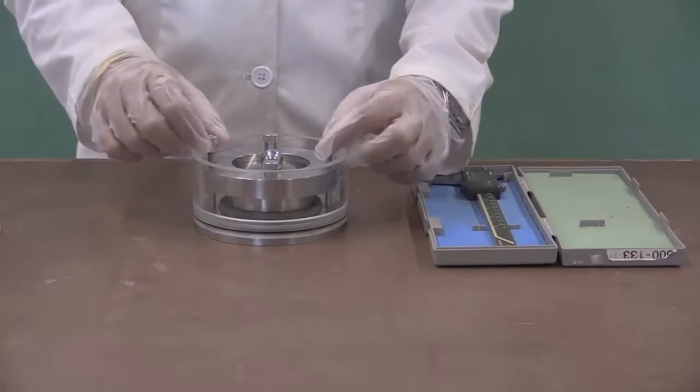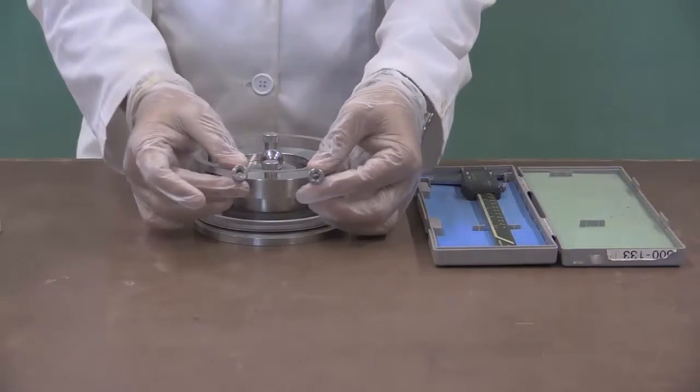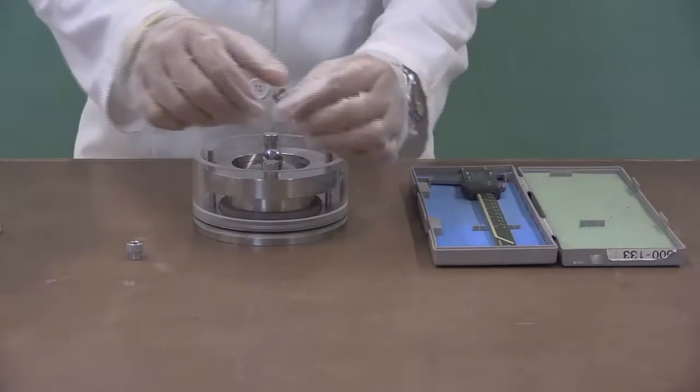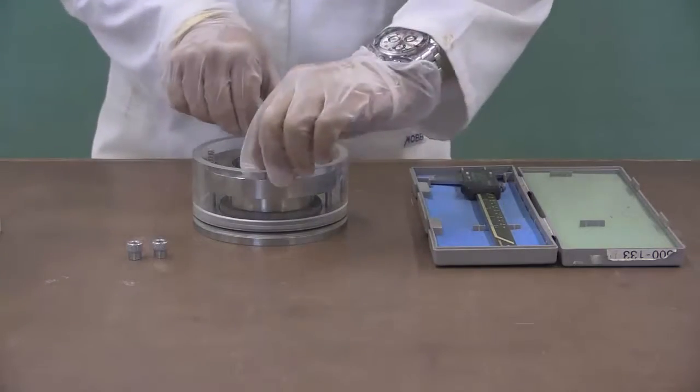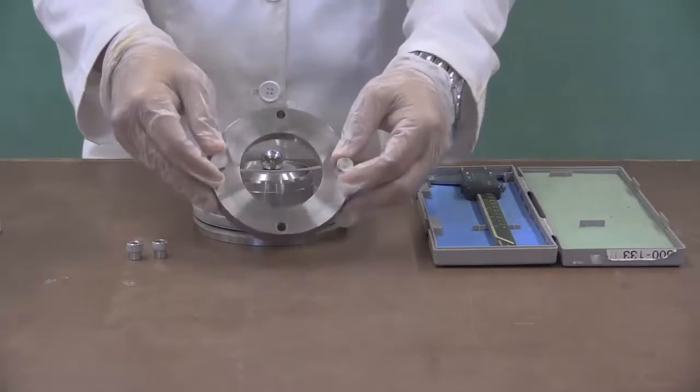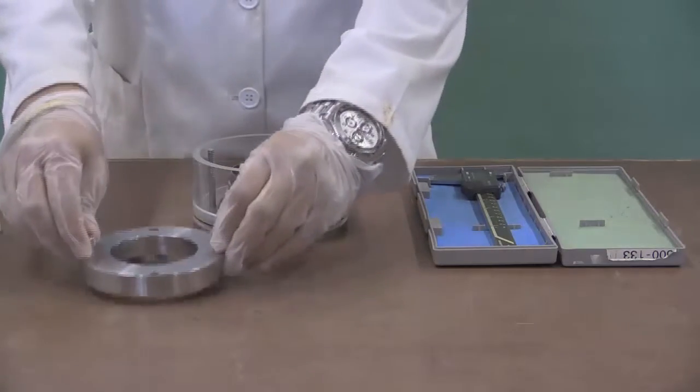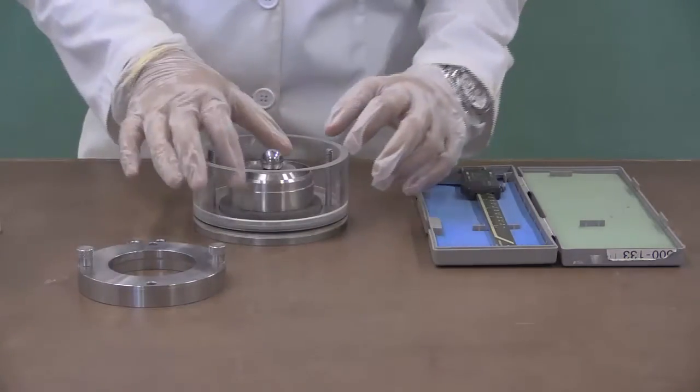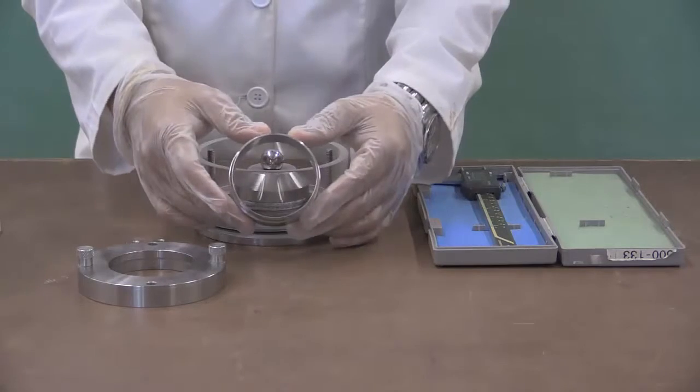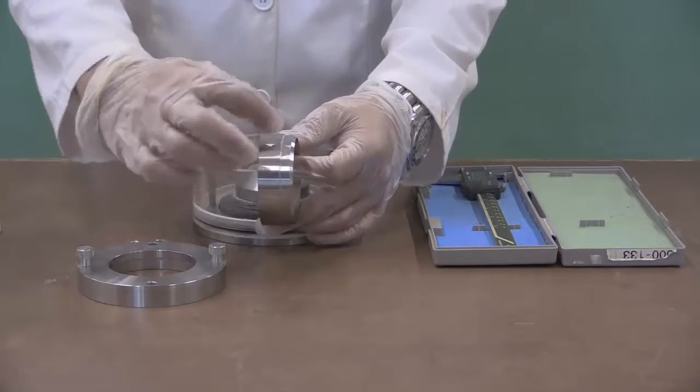You can start by unscrewing the two round nuts that hold the positioning ring in place. Take the positioning ring out of the oedometer cell and this will provide access to the rigid oedometer ring. Take the oedometer ring out. Note that it has a sharpened edge at the top.